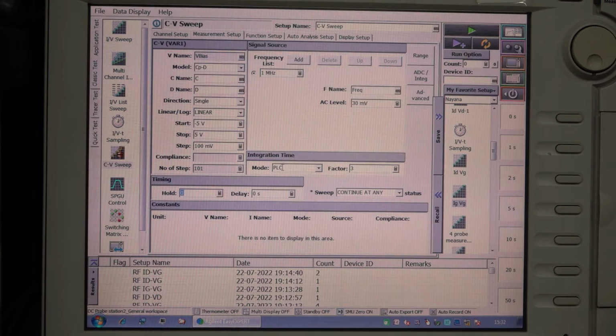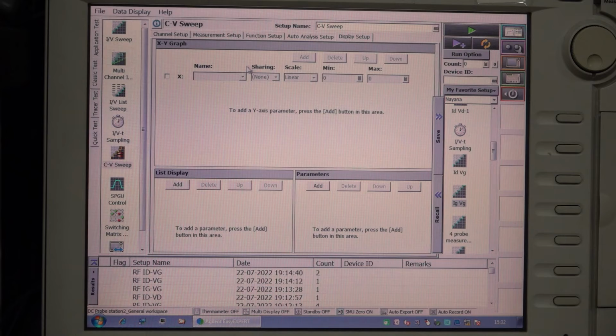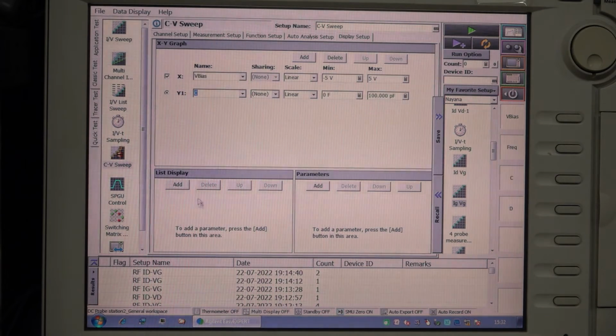This is the power line cycle for averaging the measurement values. If you put a factor of 3, it will take 3 cycles, average them, and give 1 value. So the data will be much more accurate without the noise. In the display data, I can select bias voltage and capacitance. In the data export, I can select bias voltage, frequency, capacitance, and dissipation factor.